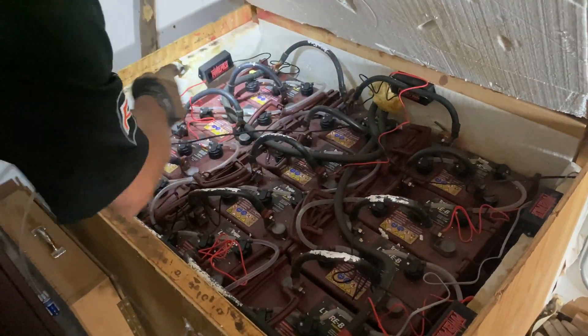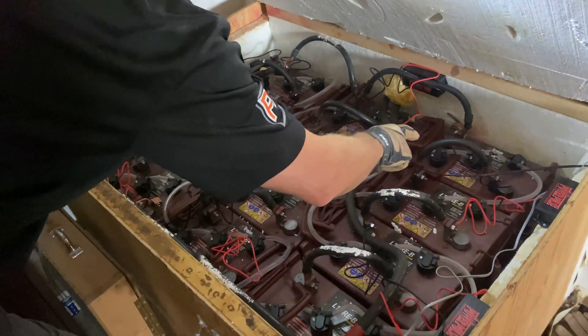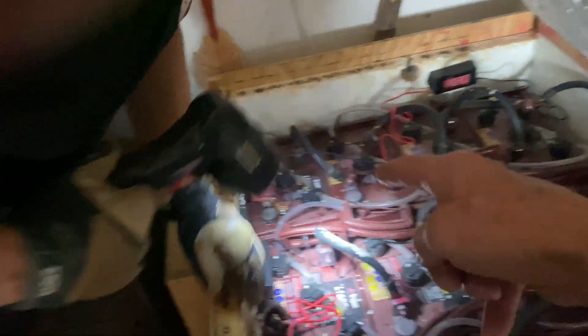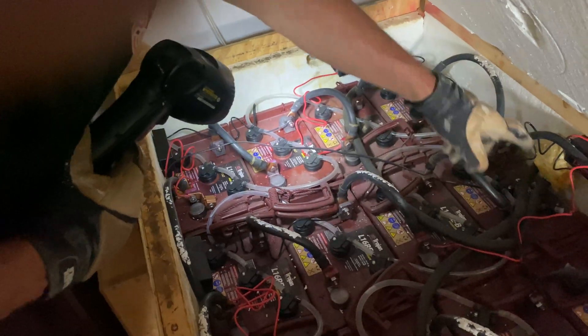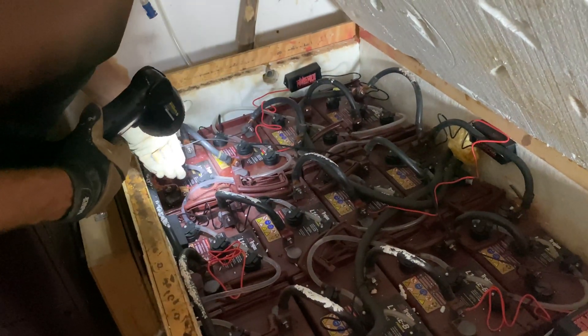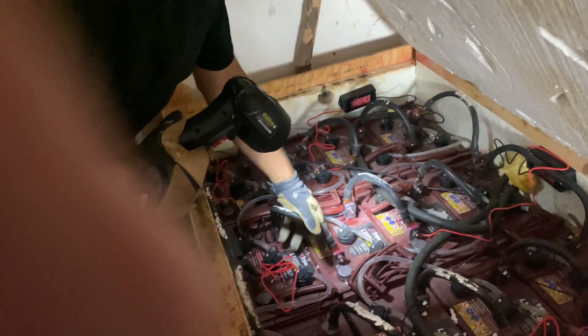The windmill came in here and then went over to where it was cut off, probably over in that corner, looking like he was trying to energize all the batteries with the windmill. But there was no disconnect or fusible disconnect out there for the windmill coming in, so when that lightning energy hit, I'm so surprised the batteries didn't explode — other than the system had really good grounding.